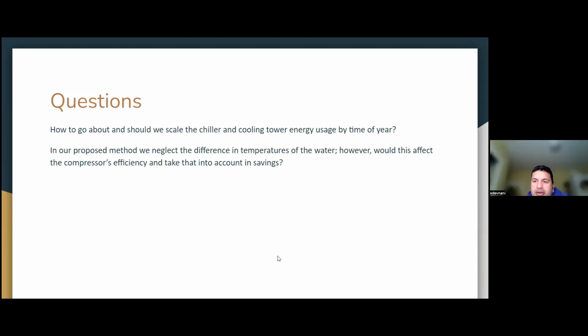I don't know if these guys are in your group, but they are golden right now for you. All you have to do is get them to open eQuest for you, and there is a biquadratic performance curve that is standard for all chillers that's provided for you. There's one for a centrifugal chiller, water cooled, one for a screw chiller, one for a scroll chiller, all of the chiller types. You can get the performance curve coefficients and the biquadratic equation from there. That biquadratic is a function of chilled water temperature and ambient wet bulb temperature. Aha, condensing temperature, right? Ambient wet bulb temperature is connected to condensing temperature and outside air temperature. Keep coming back to psychrometrics, people.